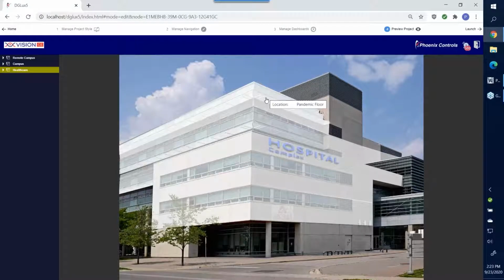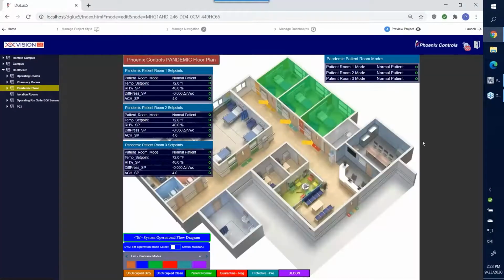We need more of the pressurized zone. So in conjunction with a Phoenix system, it's very easy to manage typical patient rooms, and then easily convert them over to what might be considered an isolation and/or pandemic application.